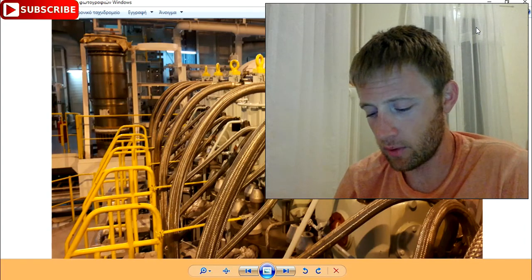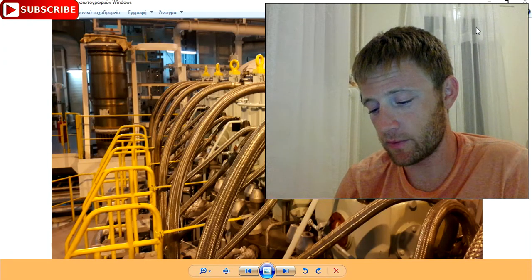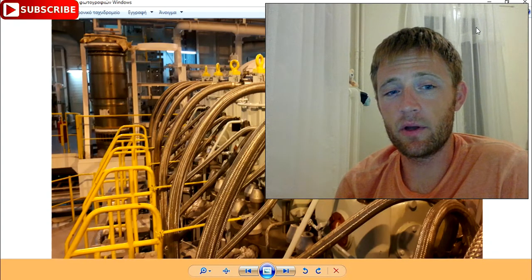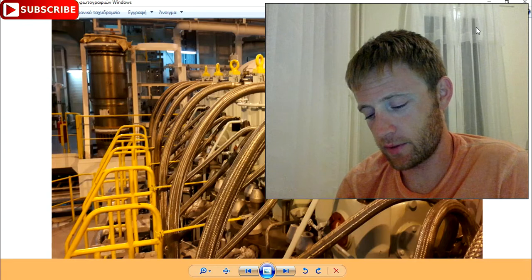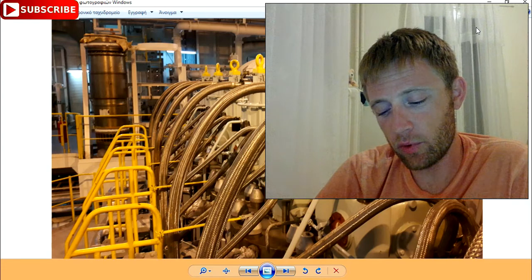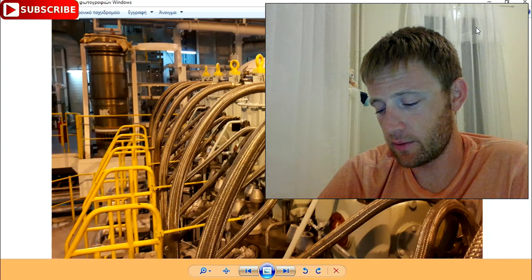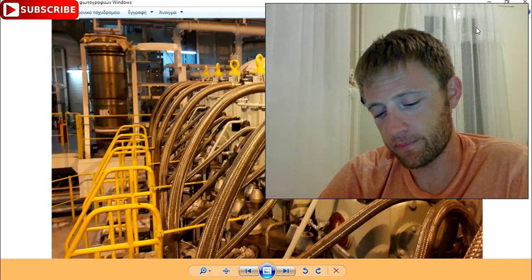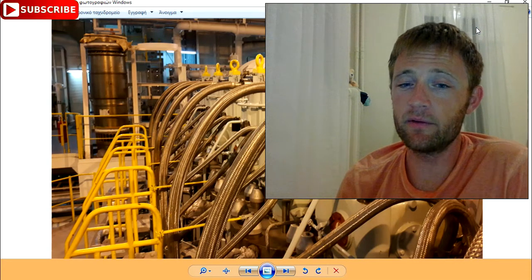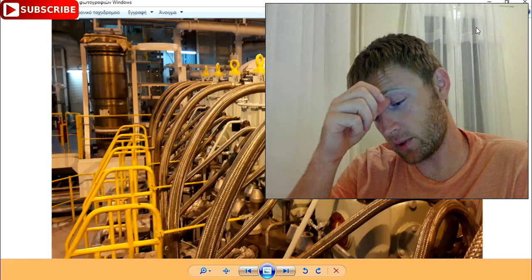This is correct. Number 8. 4 times a year we take samples. 4 times per year. That means every 3 months we take samples. Number 9. 2.5 bar differential pressure is set for the central filter of oil. That means if the differential pressure reaches 2.5 bars, there will be an alarm.